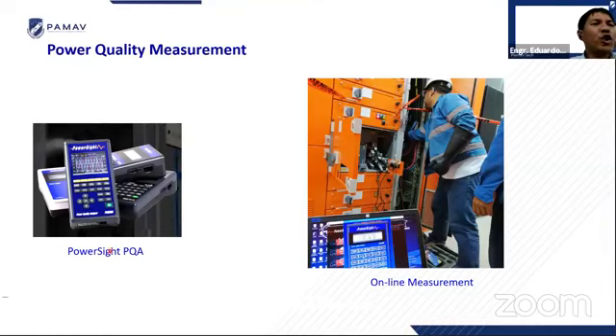The difference of this one is that we can measure up to 5 kilohertz. Remember that the IEEE standard states that the limit to measure is less than 9 kilohertz. Those standard PQAs in the market mostly go only until the 51st harmonic. So if you multiply 50 by 60, that is only 3 kilohertz. So this PowerSight is up to 5 kilohertz.